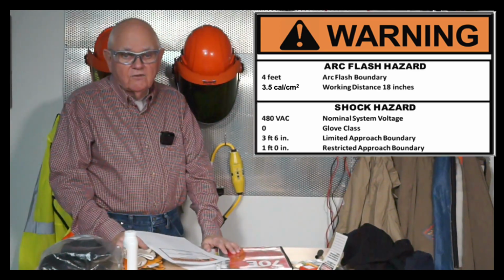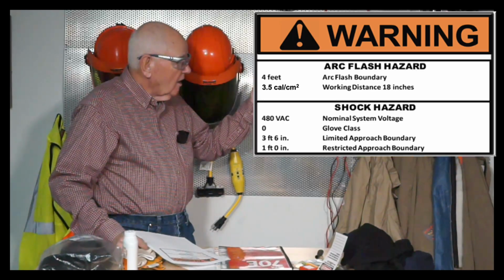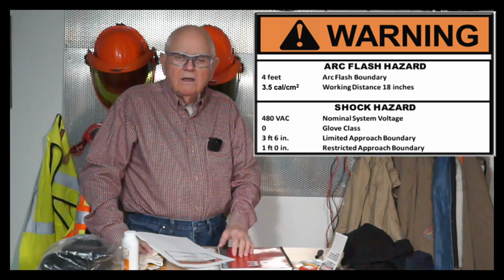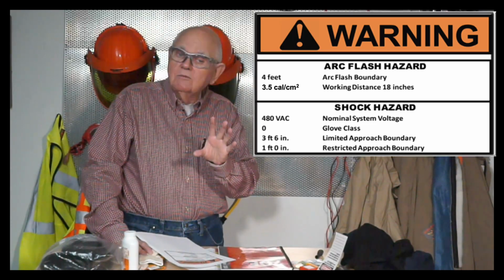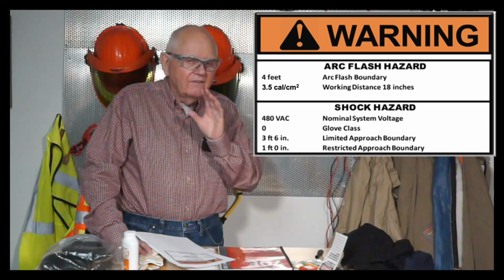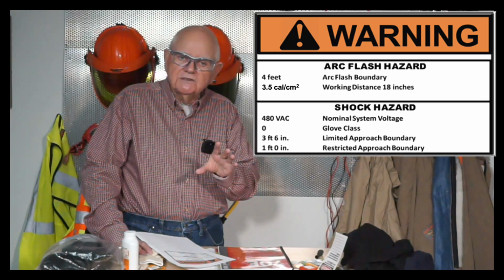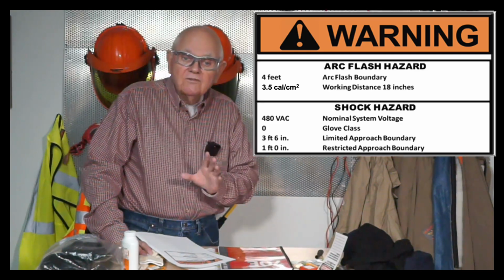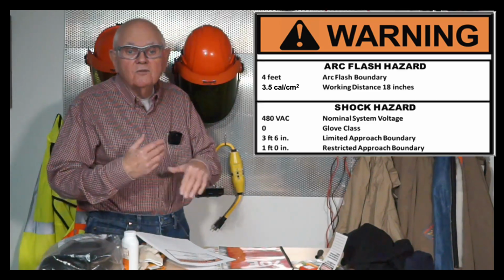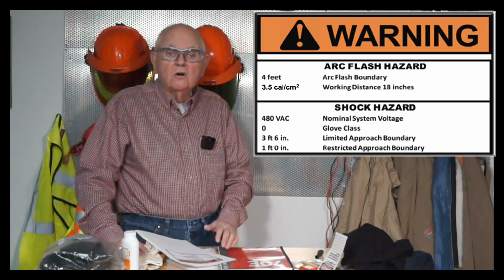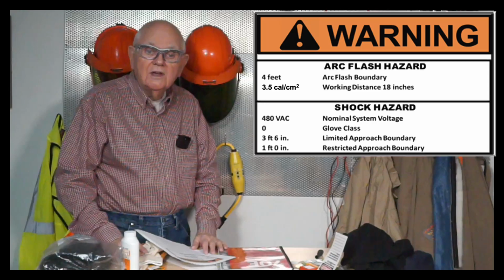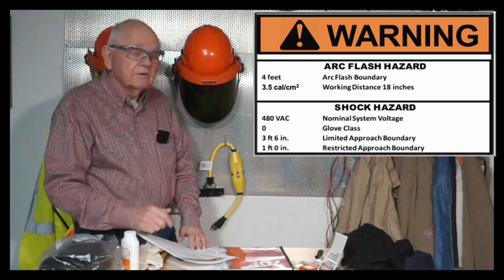That doesn't give us a lot of information. In fact, this label says warning, arc flash hazard, shock hazard. Sometimes we see those generic labels and they don't have anything else on them. That doesn't meet the requirements of NFPA 70E. So I have to have specific requirements. In fact, the informational note in the National Electrical Code refers us to the 70E standard as to what exactly we must have on this particular label.